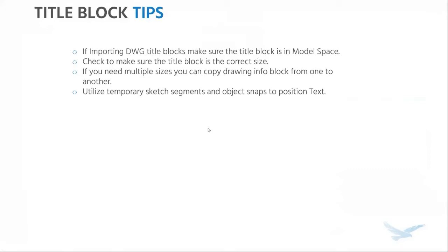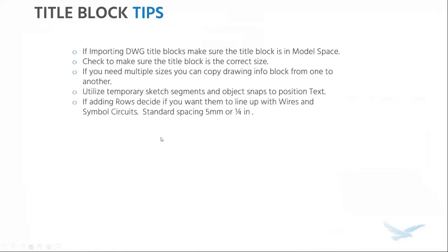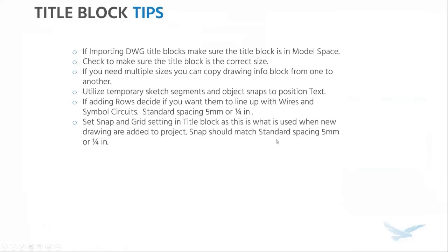Utilize temporary sketch segments and object snaps to position your text. I use this tremendously when setting up title blocks — if I need to center text in a box, I draw a diagonal line across it, use my midpoint snap, and then delete that diagonal line. Also, if adding rows, decide whether you want them to line up with your wires and symbols. Remember, the standard snap spacing for multi-circuit symbols is five millimeters or a quarter inch.